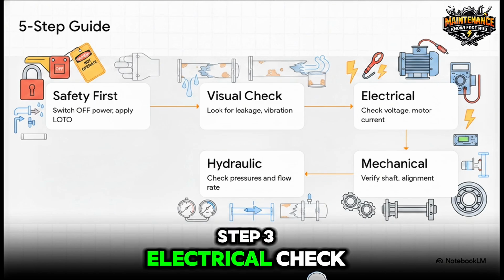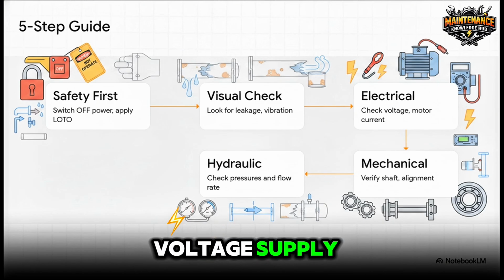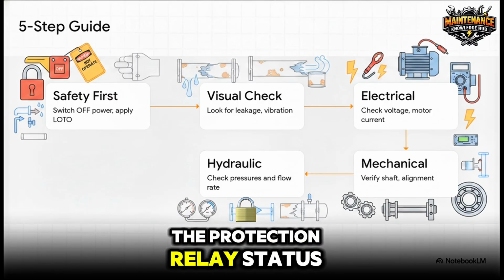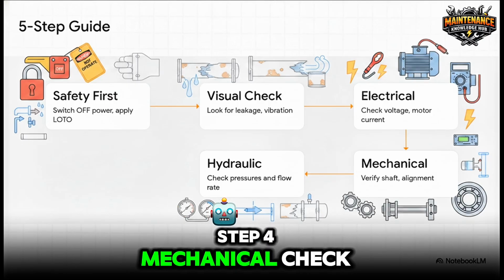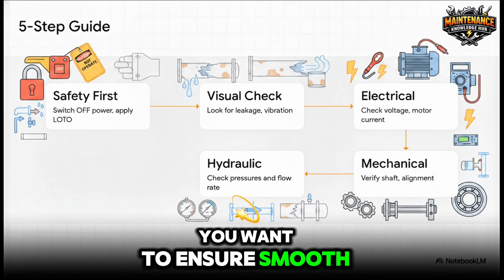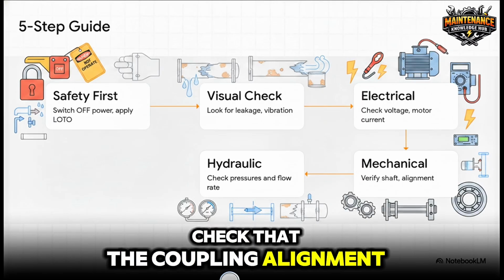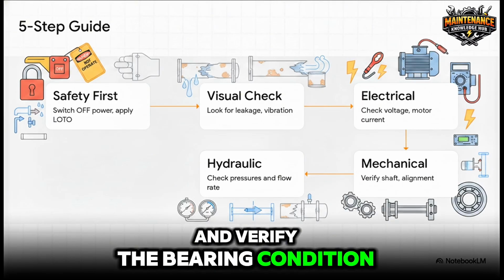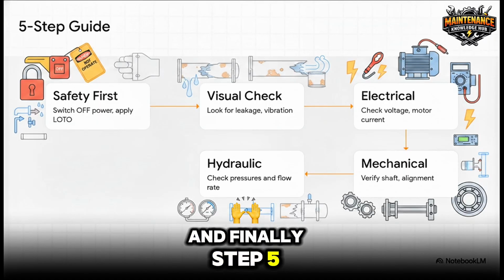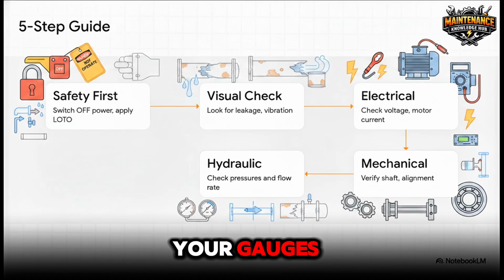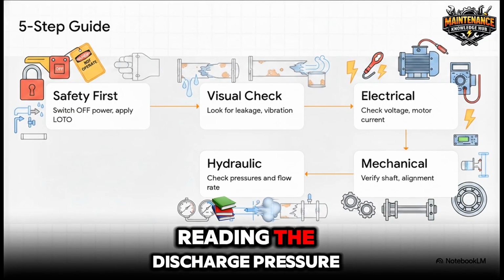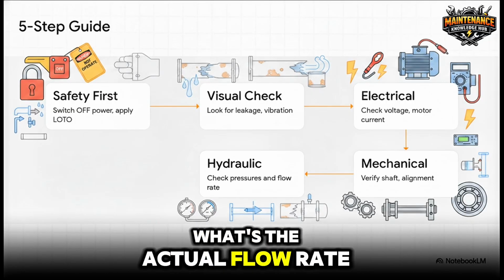Step 3. Electrical check. Let's look at the voltage supply, the motor current, and the protection relay status. Step 4. Mechanical check. You want to ensure smooth shaft rotation. Check that the coupling alignment is good and verify the bearing condition. And finally, step 5. Hydraulic check. Go look at your gauges. What is the suction pressure reading? The discharge pressure? What's the actual flow rate?